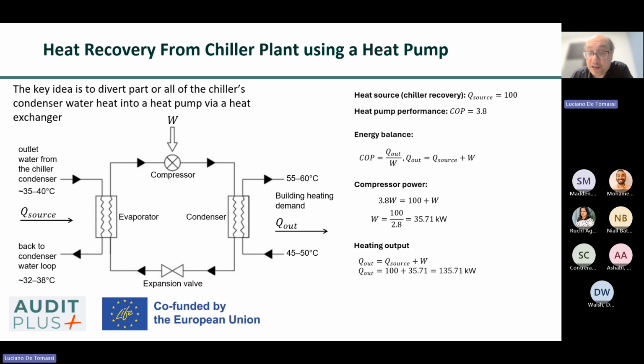The heat pump extracts energy from this loop and at the same time raises the extracted energy to a higher temperature level, such as 55 to 60 on the heating side. This creates a cascade effect where cooling demand generates recoverable heat and the heat pump bridges the temperature gap between waste heat and useful heat.